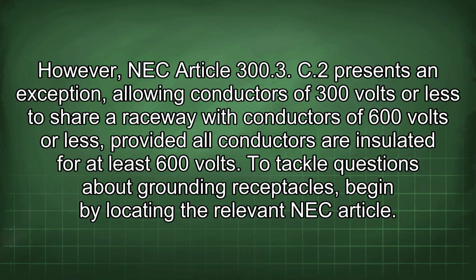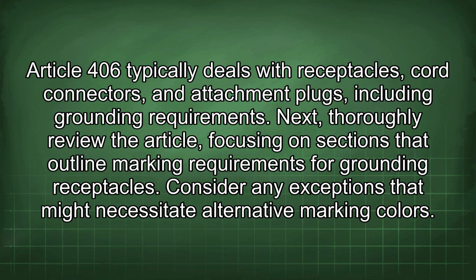To tackle questions about grounding receptacles, begin by locating the relevant NEC article. Article 406 typically deals with receptacles, cord connectors, and attachment plugs, including grounding requirements. Next, thoroughly review the article, focusing on sections that outline marking requirements for grounding receptacles. Consider any exceptions that might necessitate alternative marking colors.